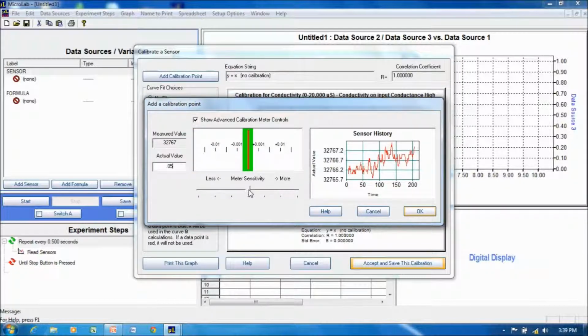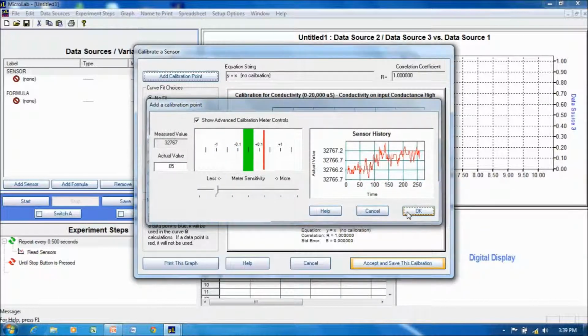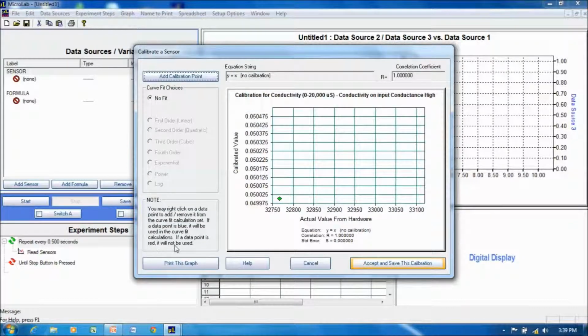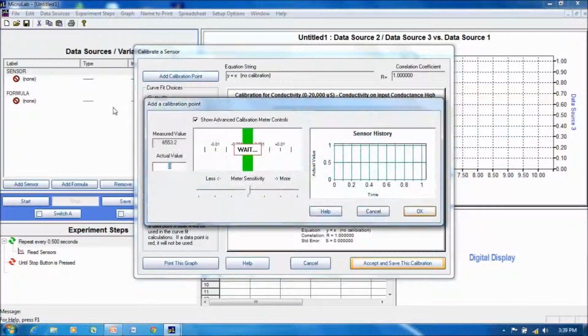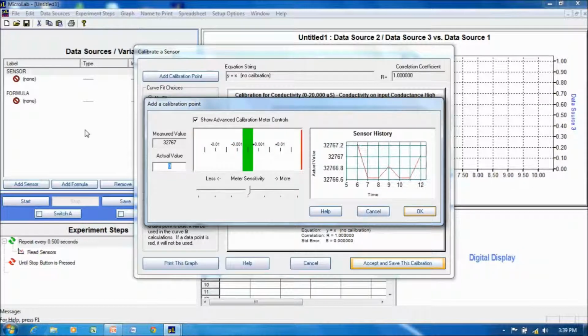I'm going to lower the sensitivity a little bit by dragging on the meter. We'll let this stabilize, and that's very good. We have our first data point. Let's add a next calibration point. And we're going to go from the most dilute to the most concentrated.